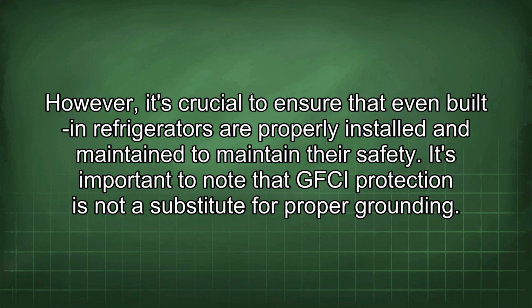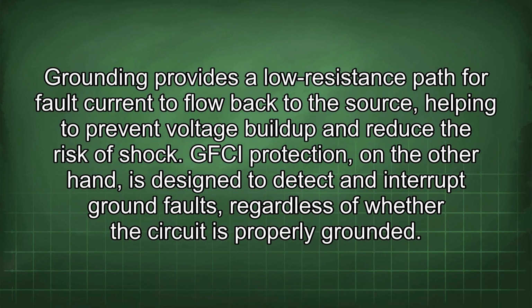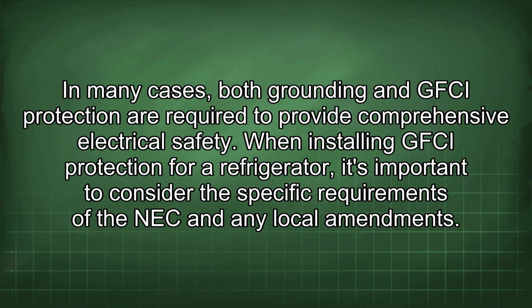It's important to note that GFCI protection is not a substitute for proper grounding. Grounding provides a low-resistance path for fault current to flow back to the source, helping to prevent voltage buildup and reduce the risk of shock. GFCI protection, on the other hand, is designed to detect and interrupt ground faults, regardless of whether the circuit is properly grounded. In many cases, both grounding and GFCI protection are required to provide comprehensive electrical safety.